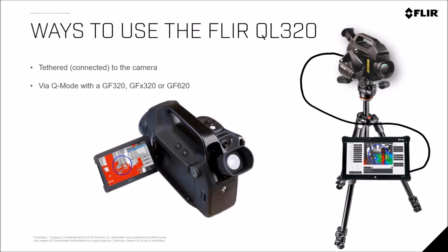As I mentioned, there's two ways to use this. Tethered when connecting to the camera. That will again be a USB mode, even though I have a GFX 320 in using this. The GFX 320 is a Zone 2 compliant device. The QL320 is also a Zone 2 compliant device, although when you open either unit up to expose a USB connection, you actually remove that Zone 2 compliance from either the QL320 or the tablet itself. So, I want to make sure that you understand that.